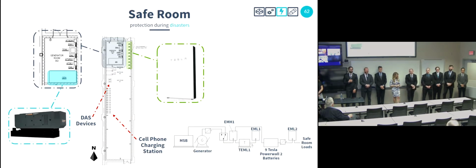I might have missed it. How are you guys dealing with the heat from the battery packs? Because it looks like those are directly in that safe room. So the battery packs are in the safe room, that's correct, not in the generator room, and those are actually specified to not give off heat in that kind of way, so that will not be an issue with that specific model. The Tesla Powerwall 2 also has an integrated water cooling system within it, which greatly reduces the amount of heat.